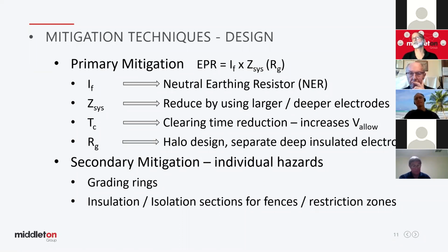Good coordination with your utility in these cases is advised. They're a good design to solve some problems. However, they do come with being specialised and need maintaining, need checking on a periodic basis to make sure that design hasn't been corrupted. Whereas your normal common bonded designs effectively can't be corrupted. They're already bonded all, as they say, and so another bond's not going to change the bonding arrangement. With this separated design, an unsuspecting installation of an LV fitting from the LV side onto part of the structure of the pad mount, say, automatically bonds across your separation and corrupts the design.